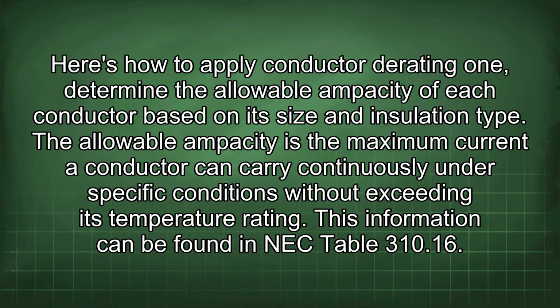Here's how to apply conductor derating. 1. Determine the allowable ampacity of each conductor based on its size and insulation type. The allowable ampacity is the maximum current a conductor can carry continuously under specific conditions without exceeding its temperature rating. This information can be found in NEC Table 310.16.